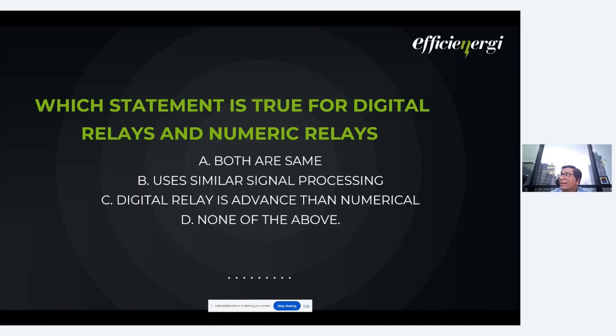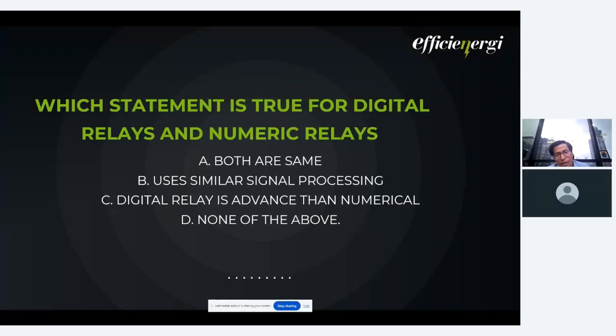Digital relay is more advanced than numerical. Okay, so basically that is not true. Actually, the numerical relays are more advanced than the digital relays, because digital relays use binary inputs, plus minus, 1 and 0. But numerical relays can take the sensing quantities directly and work on the logic and give a faster result than the digital relays. So that is not the answer.